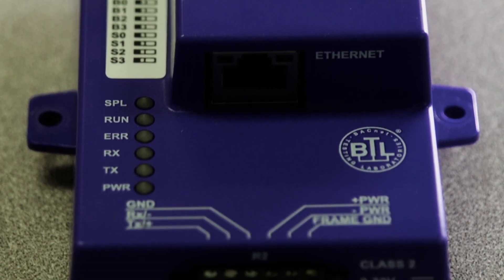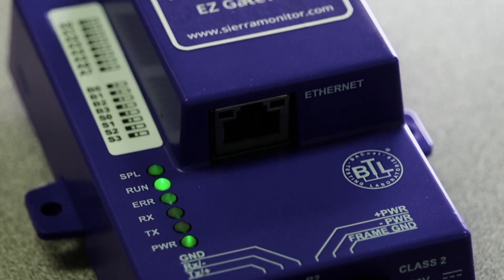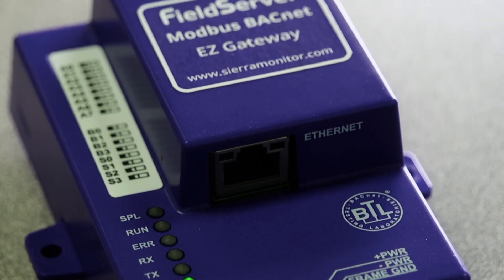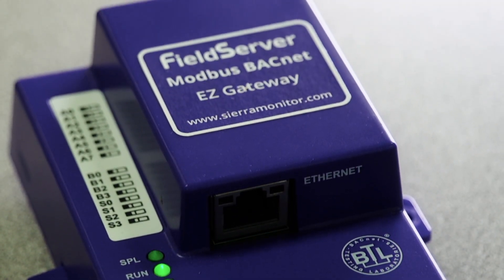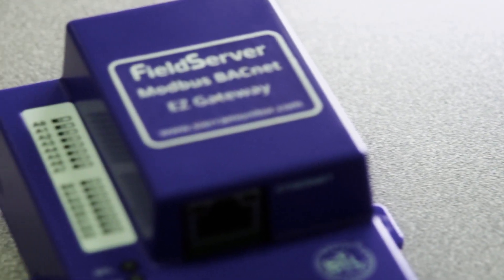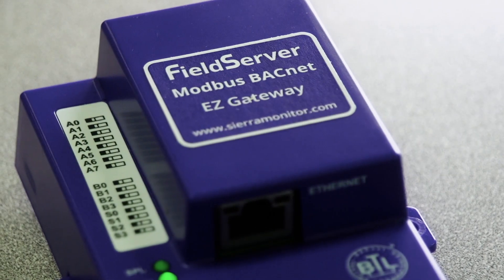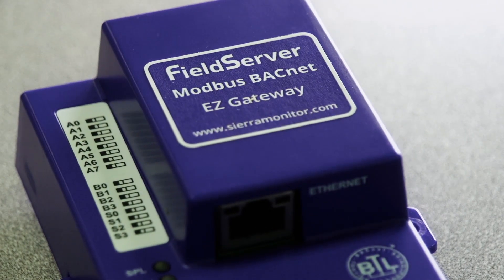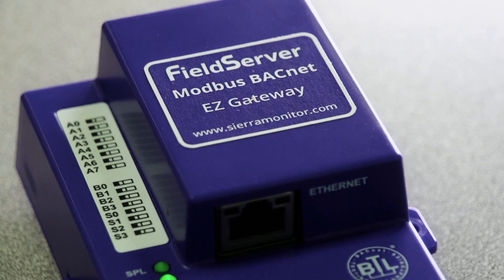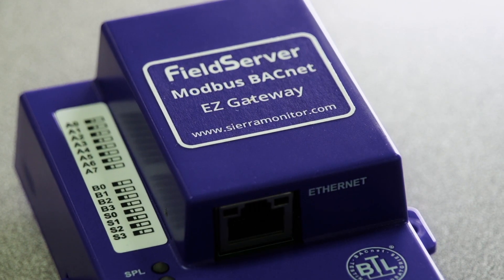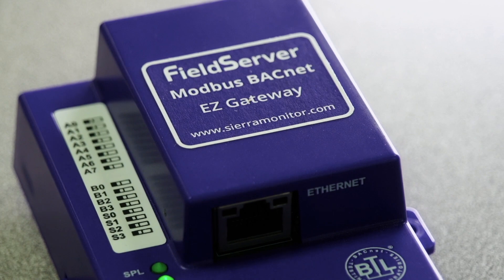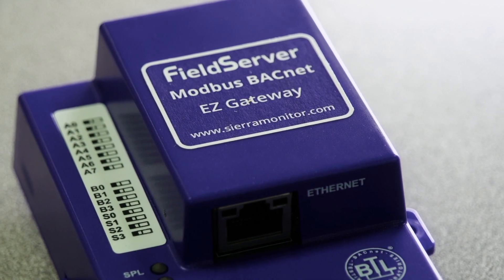Device Proxy, our unique device management feature, is an ability to represent each Modbus device as a corresponding virtual BACnet device, thereby providing granular visibility and control over each Modbus device within a BACnet management framework.